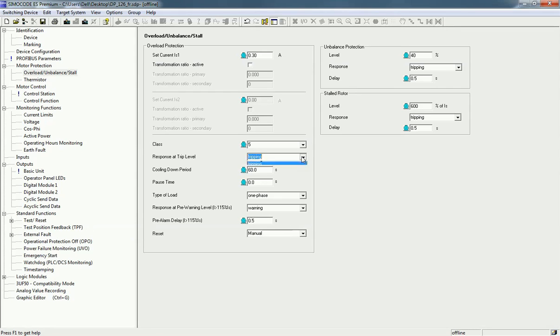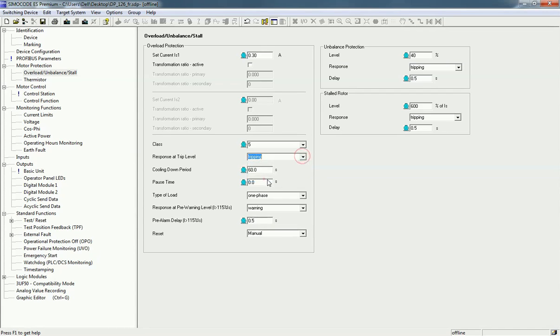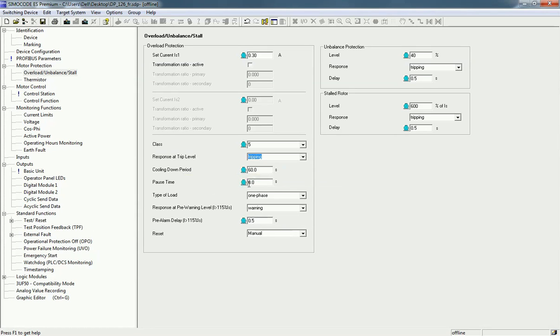If you select warning, it will only give you a message. We will select tripping. For the cooling down period — when the motor trips and heats up, you define how much cooling down time you want so the motor can run efficiently after tripping. If you want extra time, you can add a pause time. You can also define the type of load — single phase or three phase.